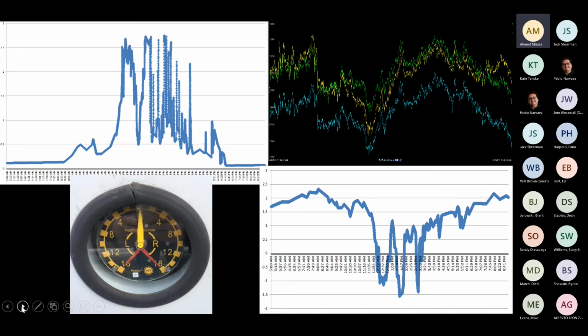But there's so much you could do. You have to go 16 raise, 16 lower, and in between, and you're stuck. But we don't really want that. I don't want the tap changer, the cap bank, or anything to move that much in a day like this. That picture on the bottom left is just the output for one day for one farm. Imagine if we have multiple farms, multiple substations, our substation equipment will not last that long. Next slide, please.